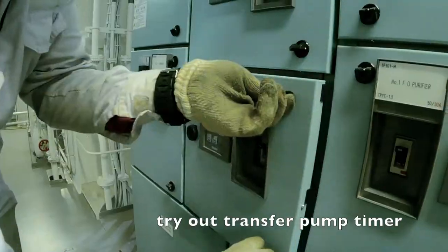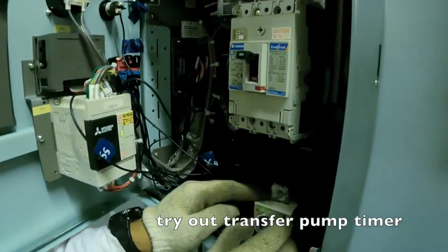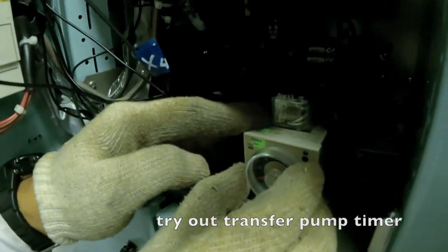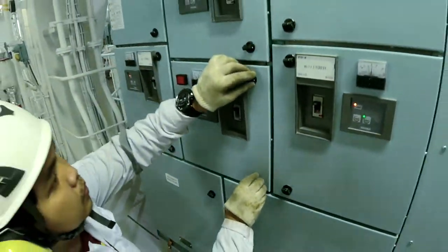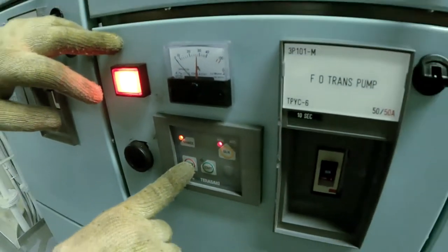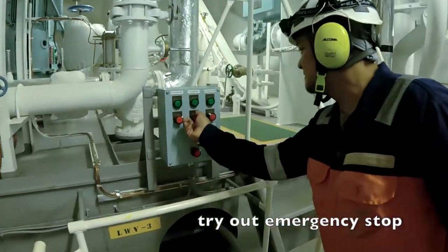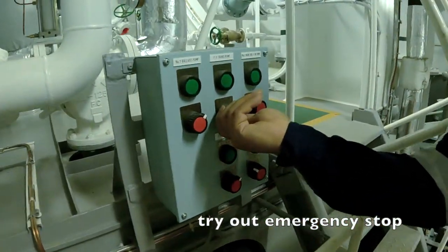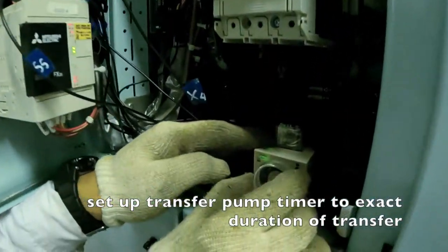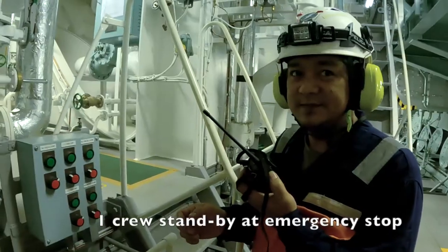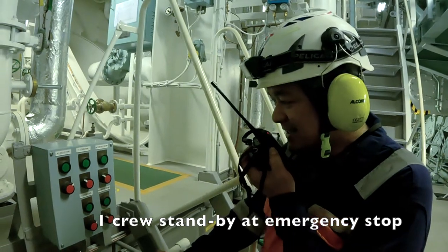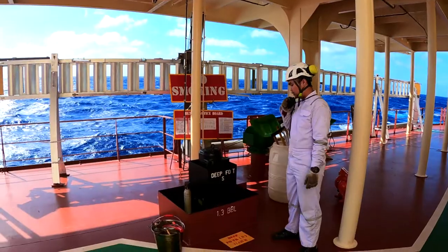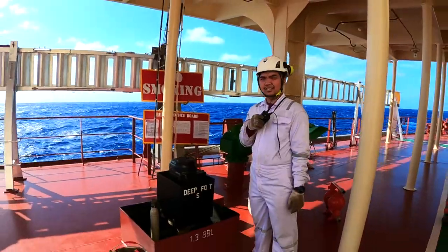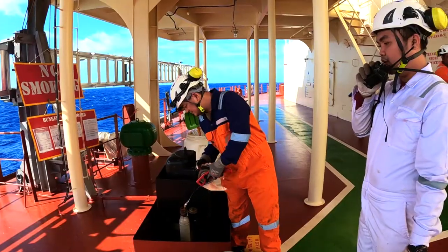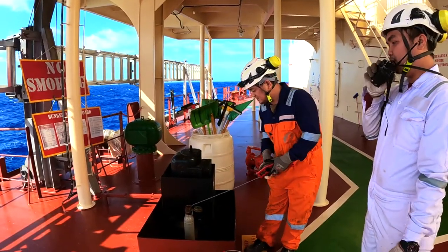Try out transfer pump timer. Try out emergency stop device. Set up transfer pump timer to exact duration of transfer. One crew to stand by at emergency stop. Notify deck officer before starting the transfer.